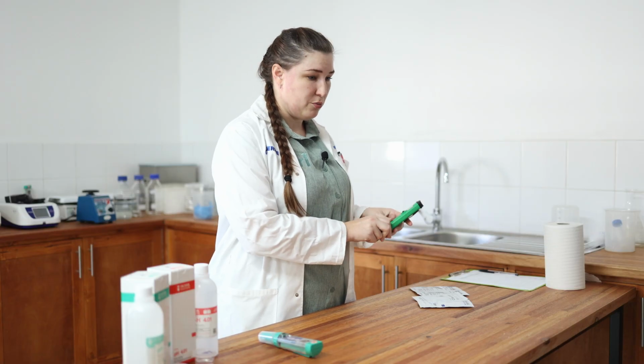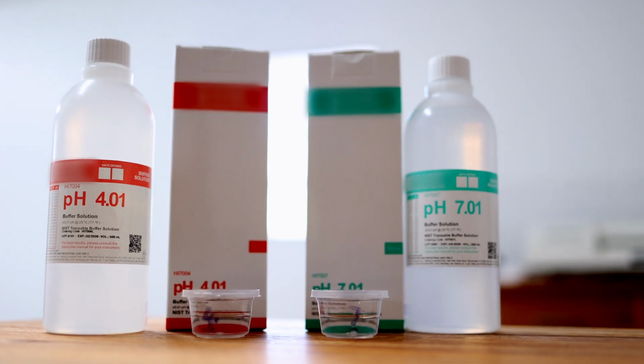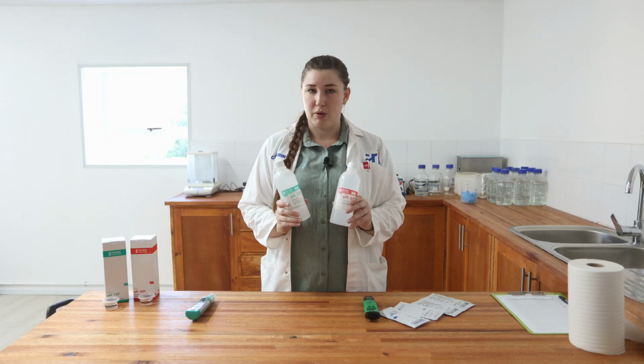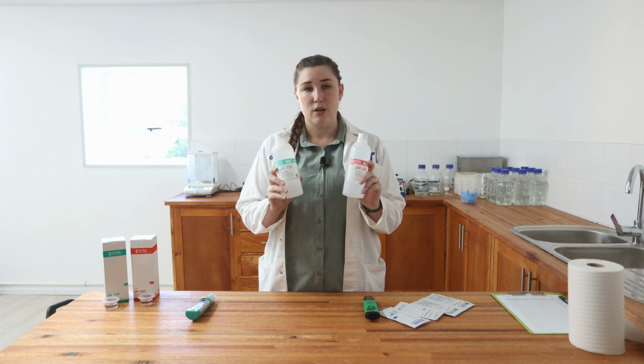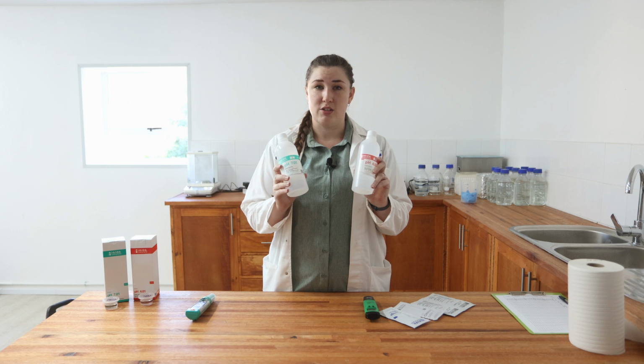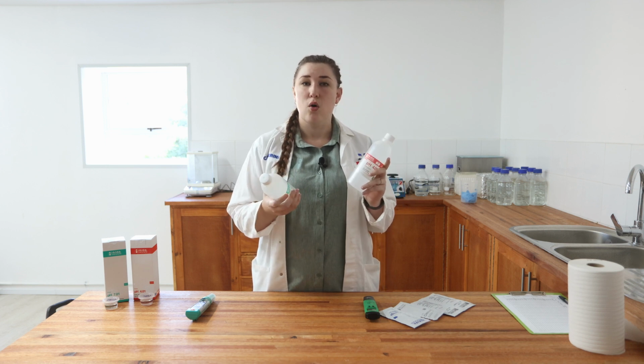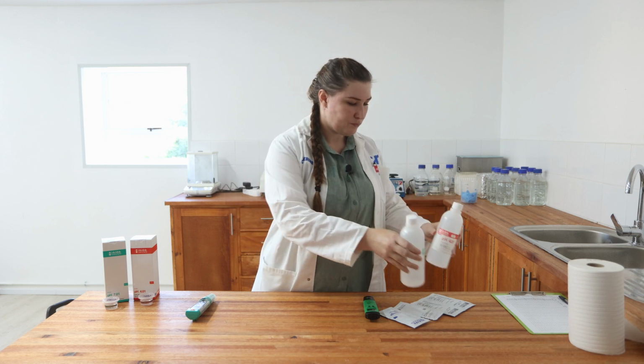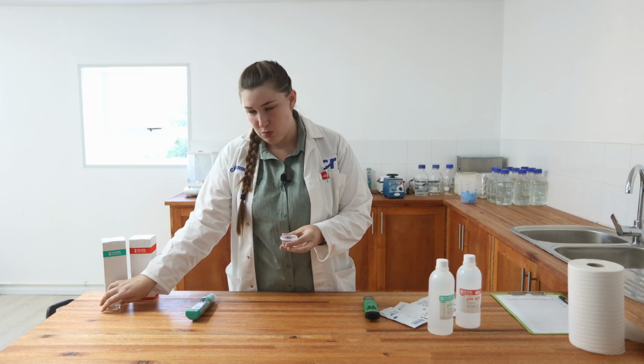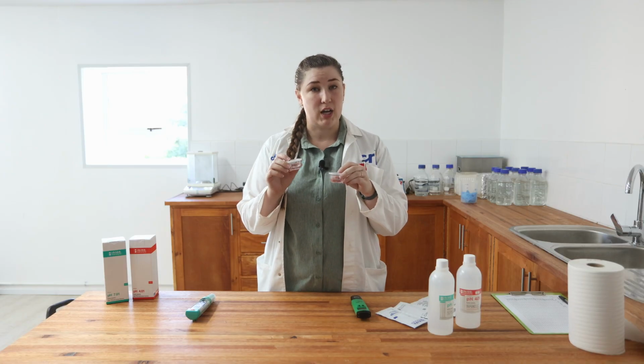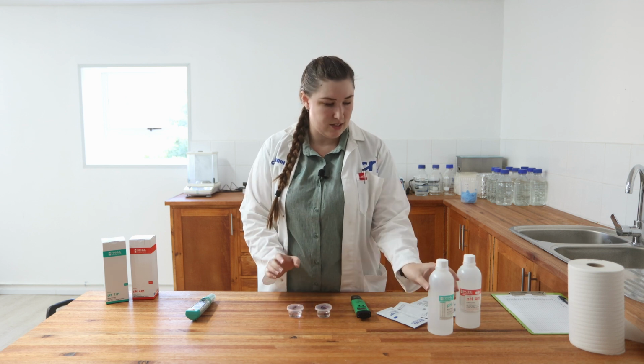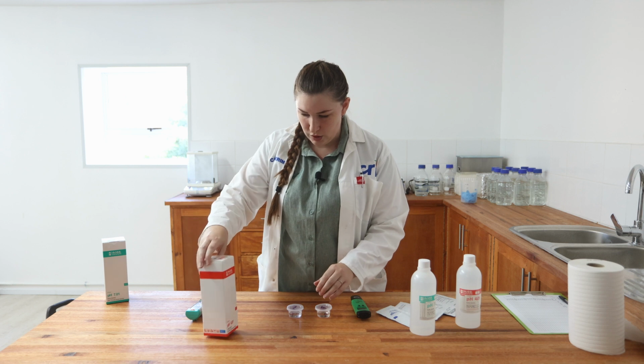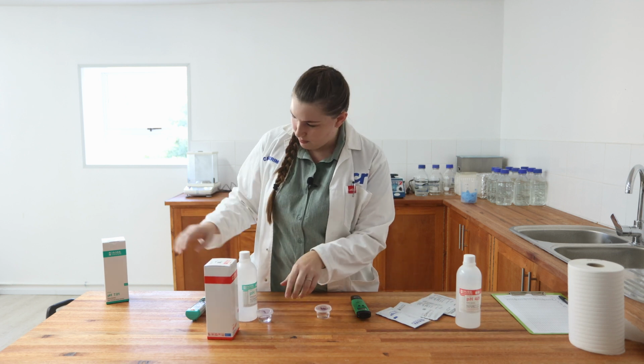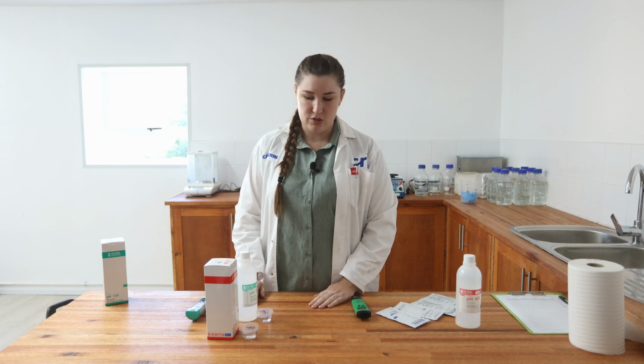To calibrate, there's a few things you need to prep. You're going to need buffer solution. Again, you might get a sample from your supplier when you first purchase your meter, but you're going to need to buy much more buffer, and you can just get them from many chemical suppliers, the one that supplied your pH meter, or from any sort of chemical supplier. What you need to do is prep some smaller containers so that you don't waste buffer. So get some small little containers, mark them with pH 4 and pH 7. Some of the solutions are colored, so in that case you can keep track of what it is. In this case, these solutions are clear, so you can also work with the boxes or the bottles to keep them allocated so that you don't get confused.